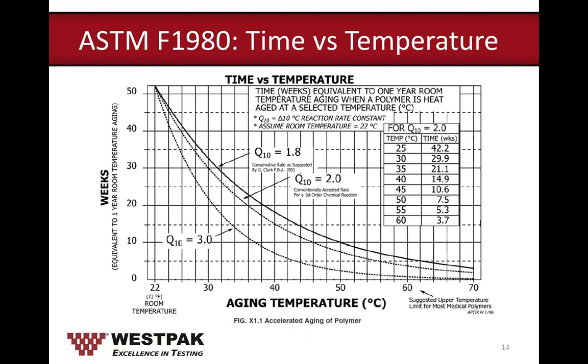Here's a graph from ASTM F1980 showing the relationship between time and temperature. Notice that as you increase the aging temperature, the time inside the chamber decreases. Every 10 degrees C increase above the ambient temperature of 25°C reduces the time by half. For example, 25°C takes about 42.2 weeks; at 35°C it takes 21.1 weeks — half the time.